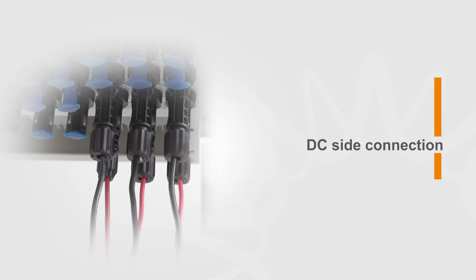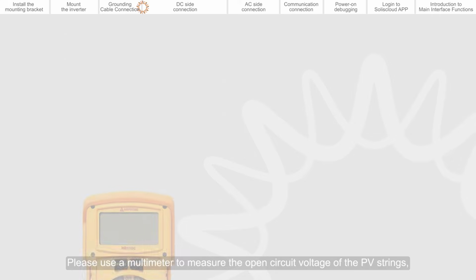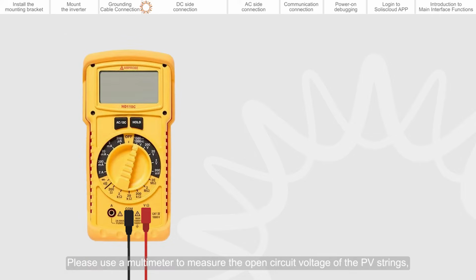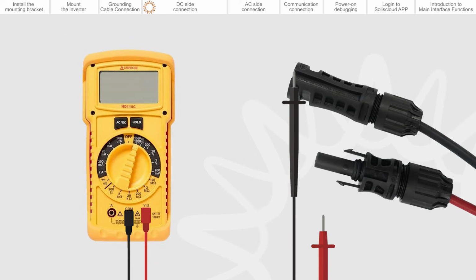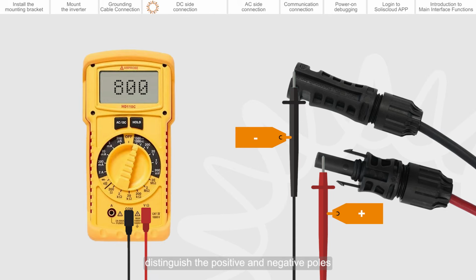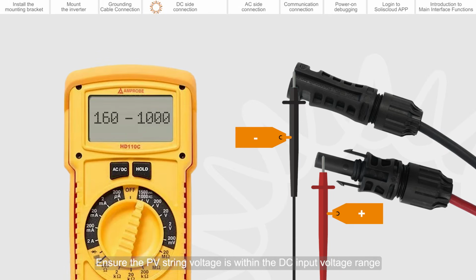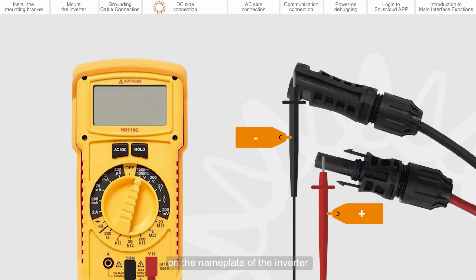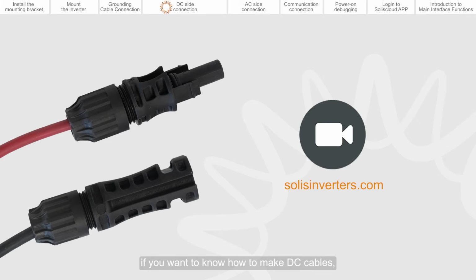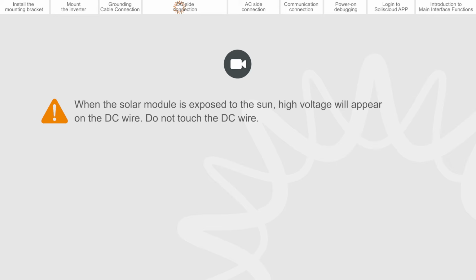DC side connection. Please use a multimeter to measure the open circuit voltage of the PV strings. Distinguish the positive and negative poles. Ensure the PV string voltage is within the DC input voltage range on the nameplate of the inverter. Qualified DC cables must be used. If you want to know how to make DC cables, please refer to the DC cable production demonstration video released by Ginlong Technology. When the solar module is exposed to the sun, high voltage will appear on the DC wire. Do not touch the DC wire.